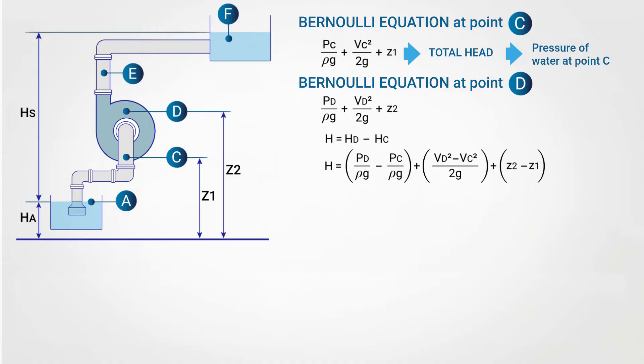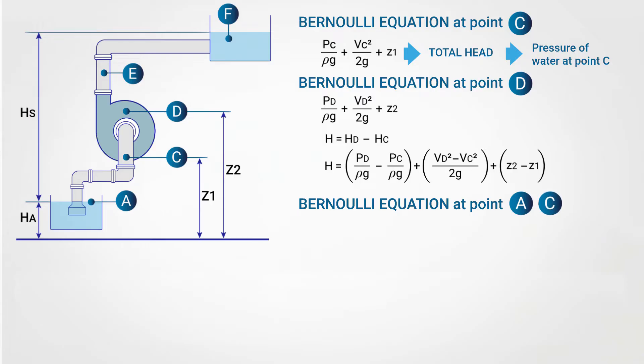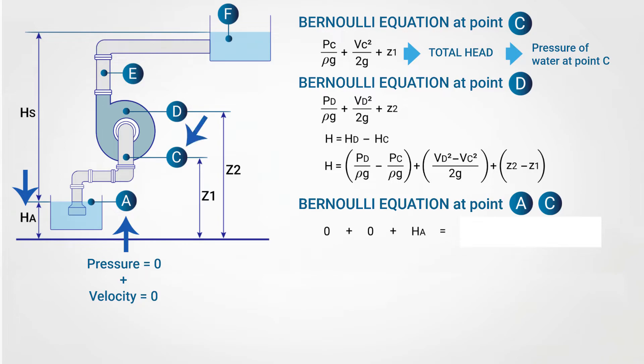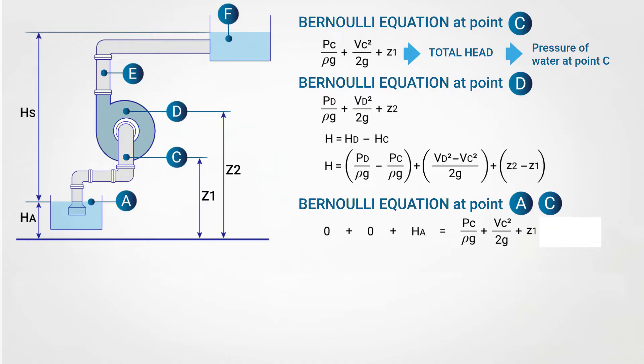It is possible to determine a relation between H and HS by applying the Bernoulli equation at points A and C. Since the water pressure at point A is zero, its velocity is zero, and the head is HA, this equals the head at C: PC/ρg plus VC²/2g plus Z1. Between point A and point C there are losses due to water entering the suction pipe and friction inside it, so the complete equation includes Z1 plus H_inlet plus HF1 (friction in the suction pipe).